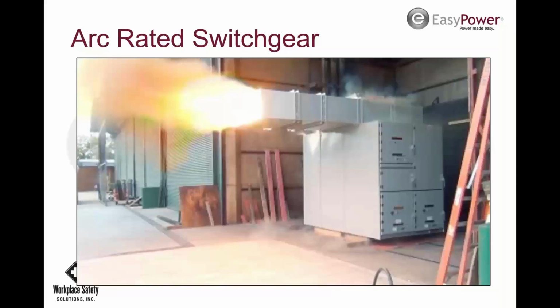There was one company that wanted to do some maintenance on the fence around the arc rated area. They said, "Is that okay?" And I said, "Well, not really." Because if that has an arc flash inside, you're going to get the same thing as if you had non-arc rated equipment inside without having PPE. So it depends what it is, but maybe you want to put people in a suit to do it, or maybe you want to shut down and do it during a shutdown. You're just shifting the hazard to another place that may be safer, but you still have a hazard there that you have to deal with.